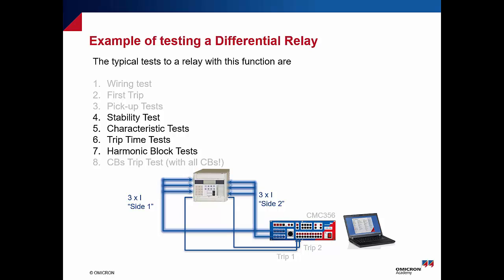file. You have to verify that your wiring is connected correctly by injecting different current values, and different voltage values in case your application needs voltage as well. These different values, you have to read them out from the relay under test, to make sure that your wiring is correct. Please consider this as very important, so as not to lose your effort and your time in case you make any miswiring or wrong wiring, because it will delay your progress in the testing.